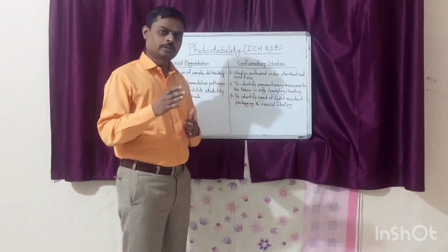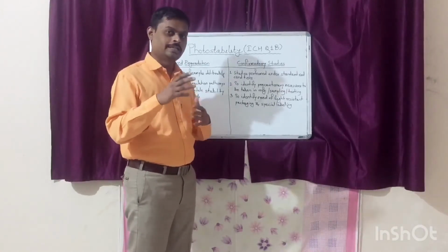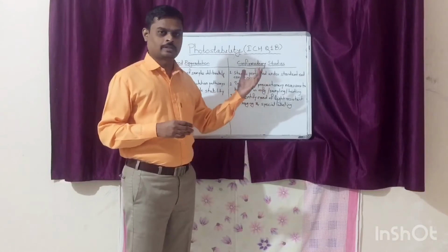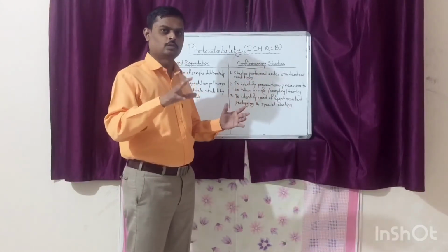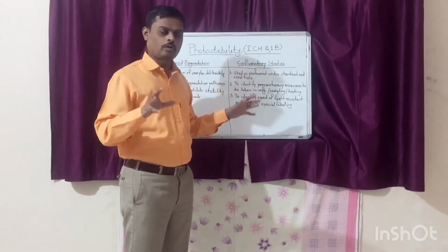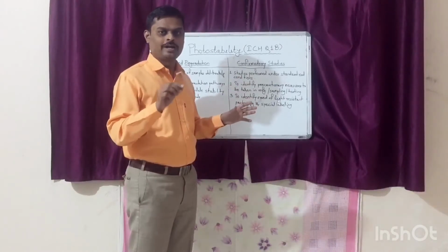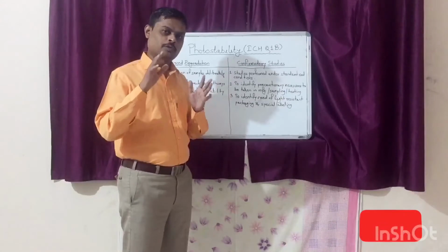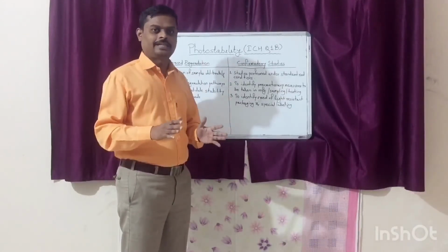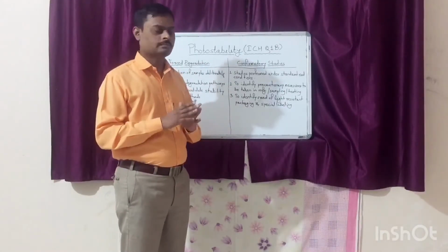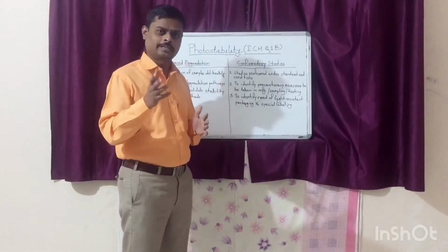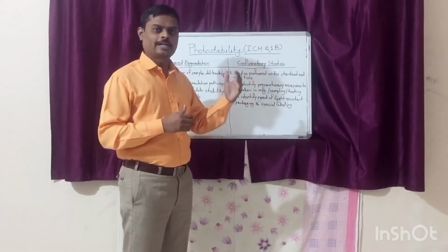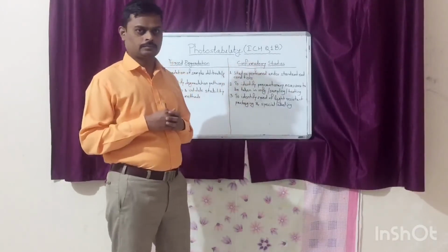Similarly, if you know the energy of your photostability chamber, you can also identify the exposure time to achieve the overall energy of 200 watt hours per square meter. For example, if the energy of your chamber is 10 watt hours per hour, then 200 divided by 10, so if you expose your samples for 20 hours, it will achieve the desired conditions.